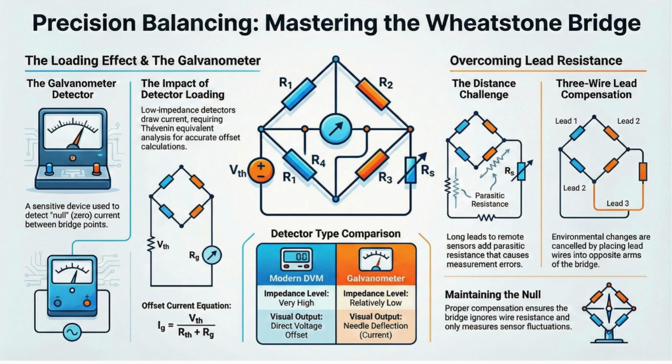The voltage drops. The source calls this the Thevenin equivalent. Basically, the number you see on the screen is lower than what was actually there before you touched it. That's just pure error. Okay, what's the third problem? Power dissipation. Yeah, heat. To get a voltage reading, you have to push current through the sensor. And current through resistance generates heat. I squared R losses.